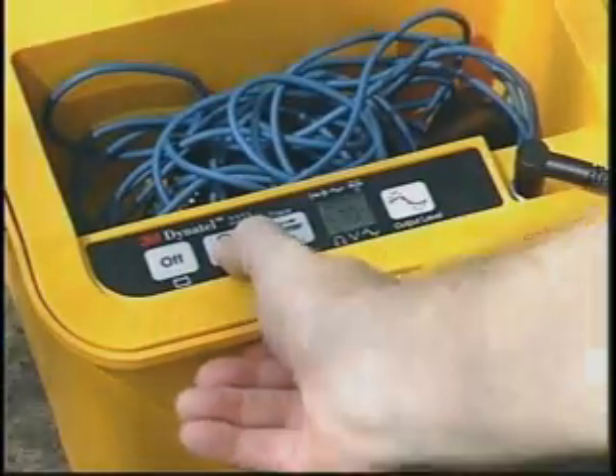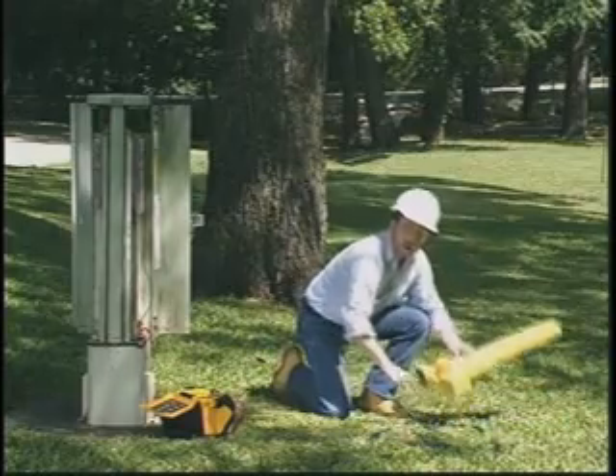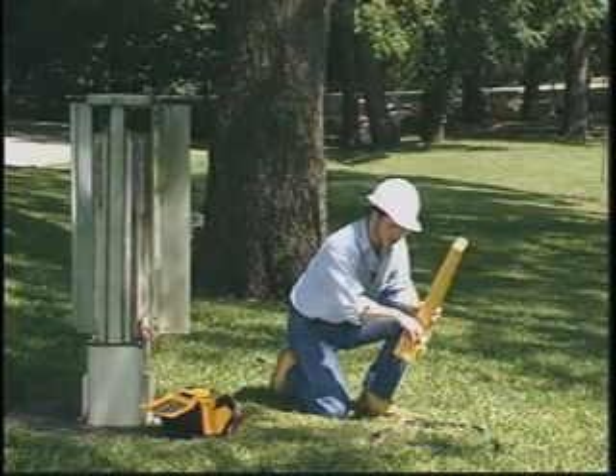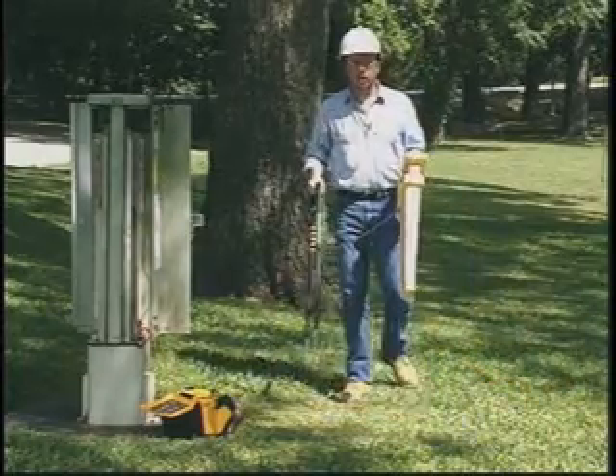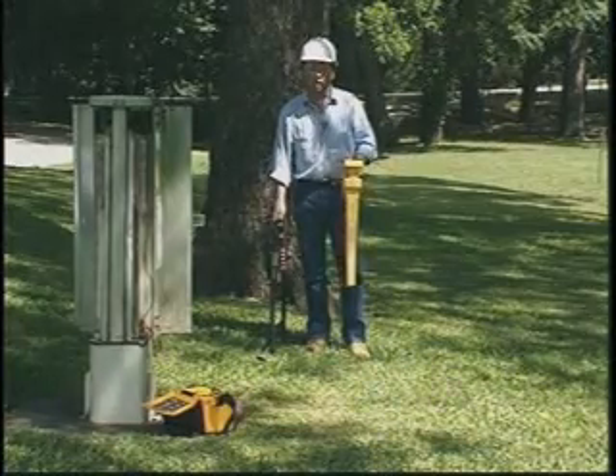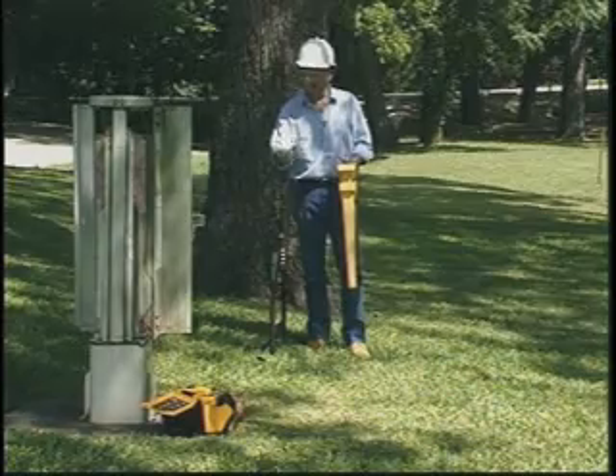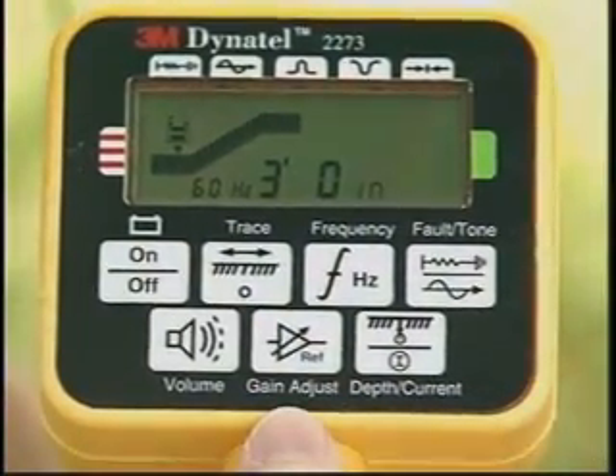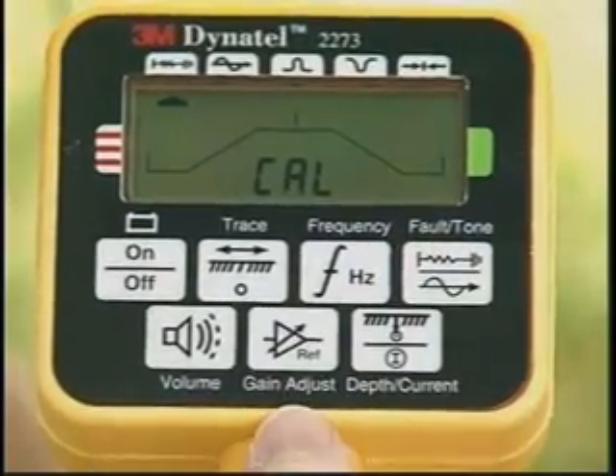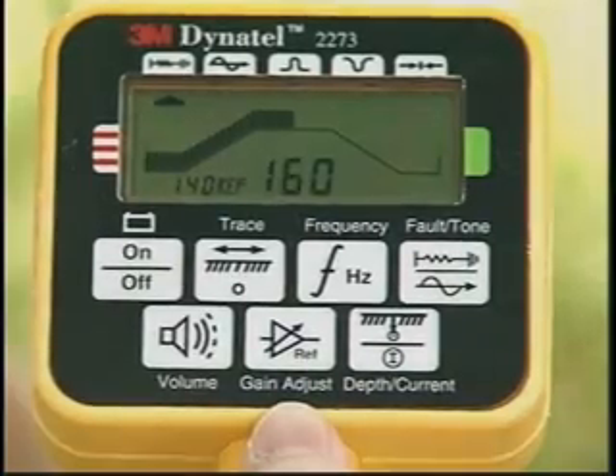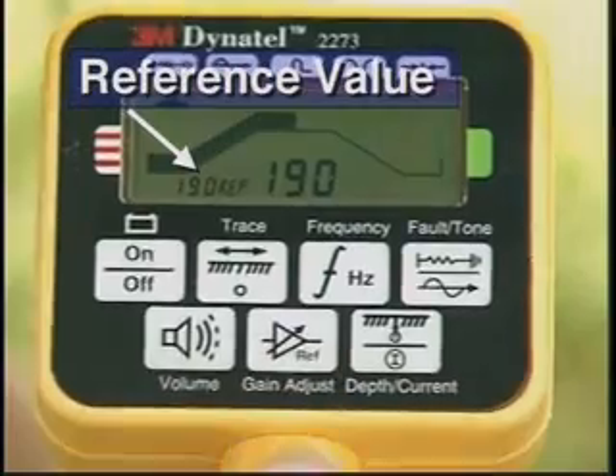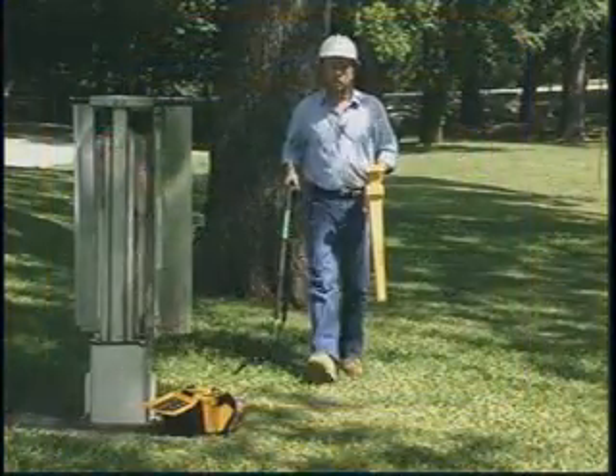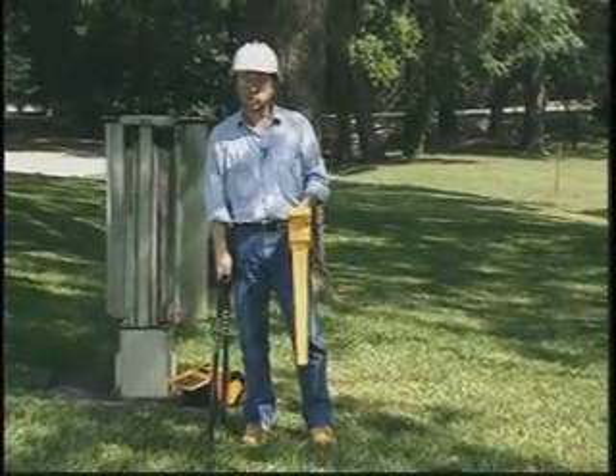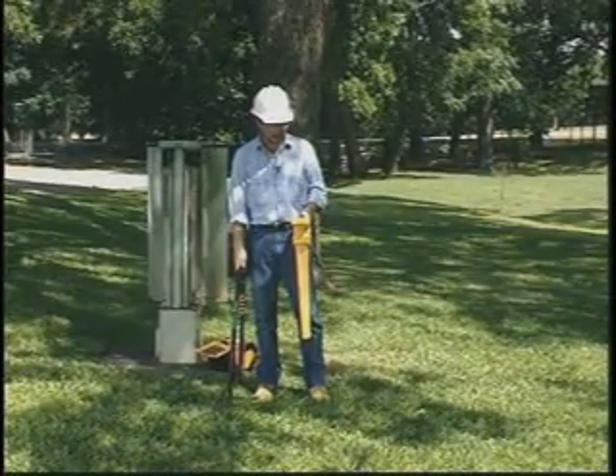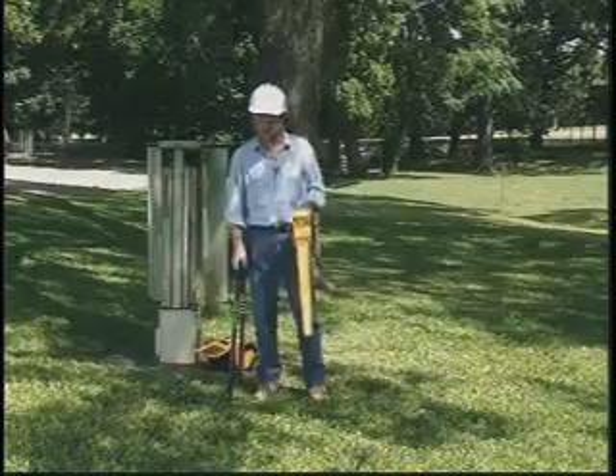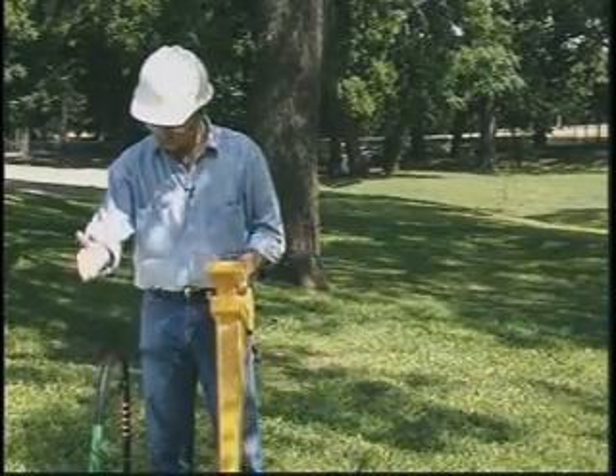Now, set the transmitter to fault mode and connect the earth contact frame to the receiver using the earth frame cable. Insert the earth frame into the ground 1 or 2 feet from the ground rod with the green banded leg toward the fault. Turn the receiver on. Activate the fault mode. Press the reference key to set the earth frame reference value. When you find a fault, you'll use this reference value to determine if it's a major fault or not. Since the receiver's bar graph is on the right or green side, it's indicating that the fault is ahead, in the direction of the green banded leg.